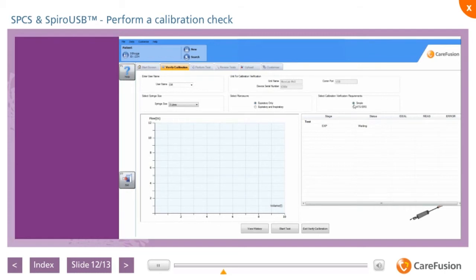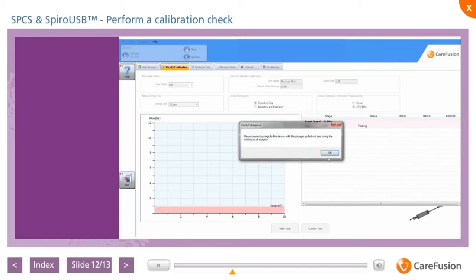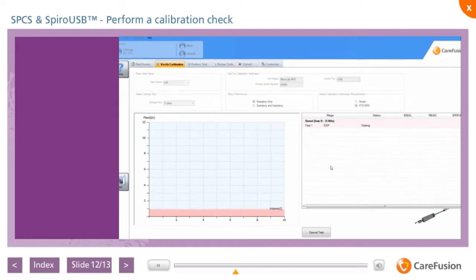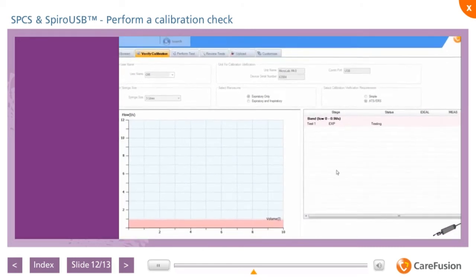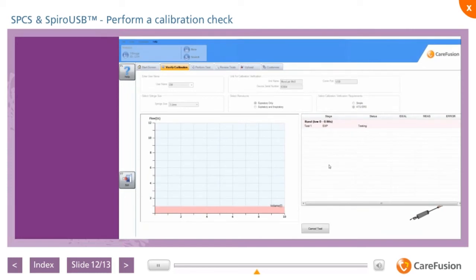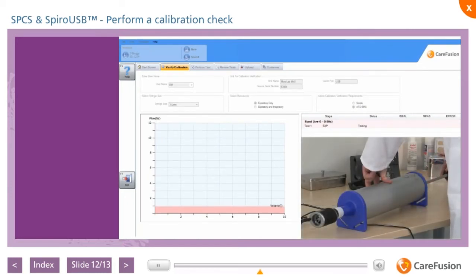Using SPCS software, calibration verification can be performed in either simple mode with a single flow rate or ATS-ERS mode at 3 flow rates. Both modes allow the option to perform expiratory or expiratory and inspiratory verification. If ATS-ERS verification is chosen, the display will show 2 colored bands. These are for guidance as to the speed the syringe should be emptied and filled. Select Start Test and, as instructed on the screen, fill the syringe by drawing the plunger out, and then empty the syringe by pushing the plunger in.